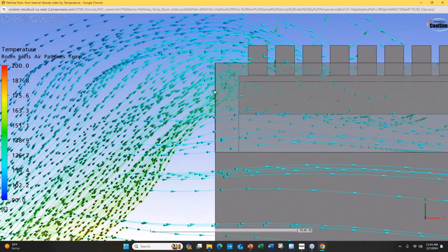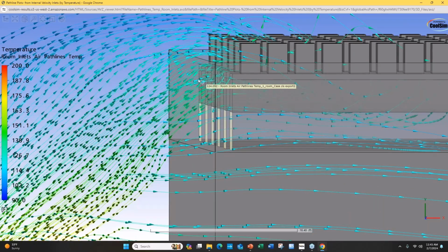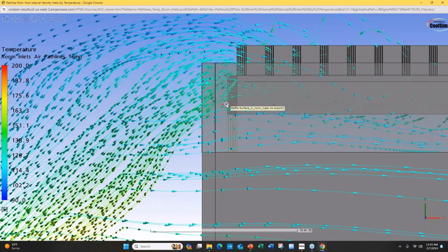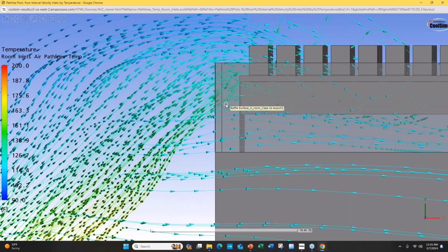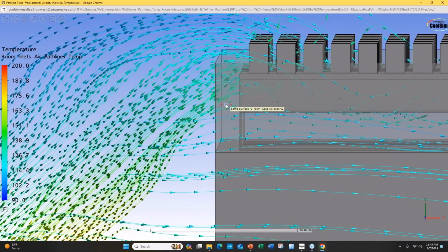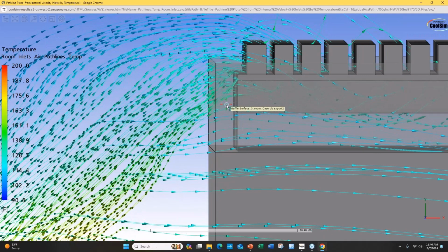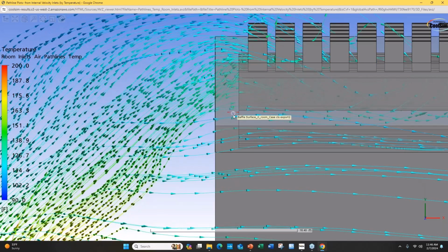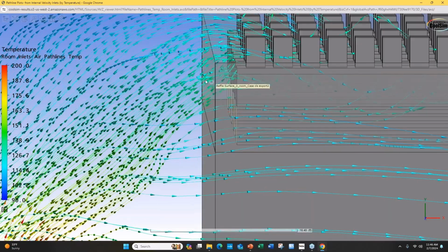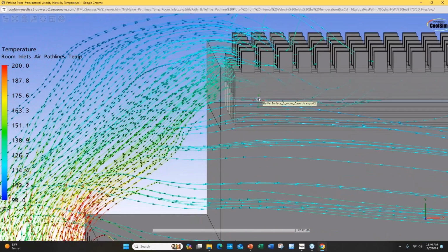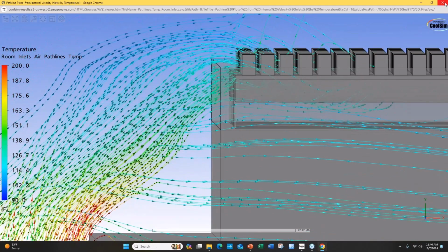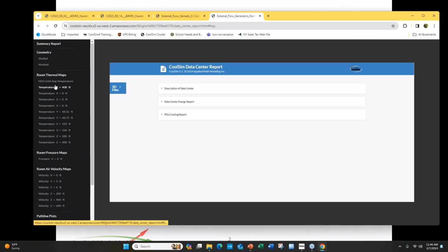So here we have percent area open set on that front screen. They usually are, and you can see it's still blowing through it. It's probably better than it was, but these screens tend to cause some of their own problems. As I mentioned, they create a low pressure inside them simply by the fact that you've got flow over the top of it, and when it goes to the other side, it creates a low pressure. But put a screen around it, and let's take a look and see if our HDU temperatures dropped.